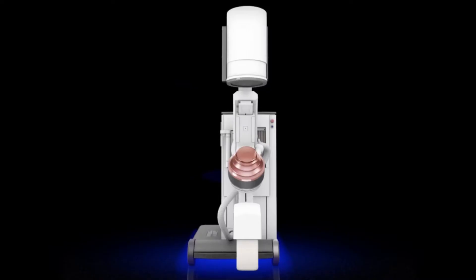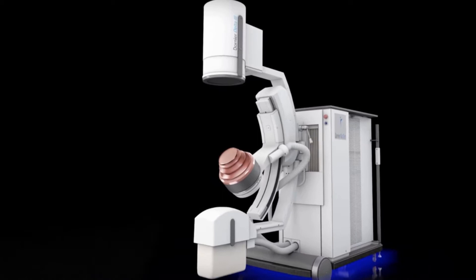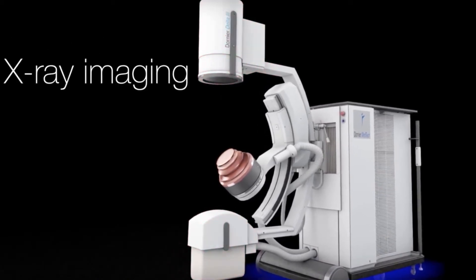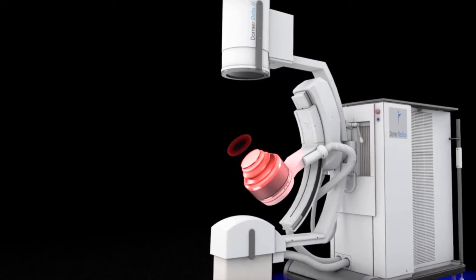What exactly does that mean? A typical lithotripsy machine has several key components. First, an imaging system to help identify the stone, here seen with fluoroscopy or the use of x-ray. And second, a shockwave generator, also usually accompanied with a lens to help focus the energy to the stone itself.